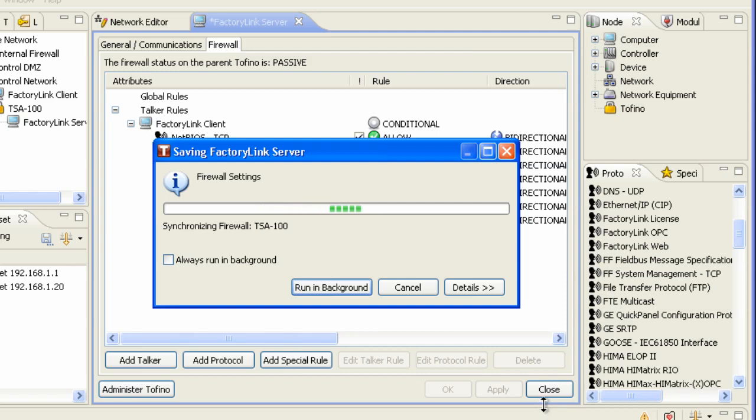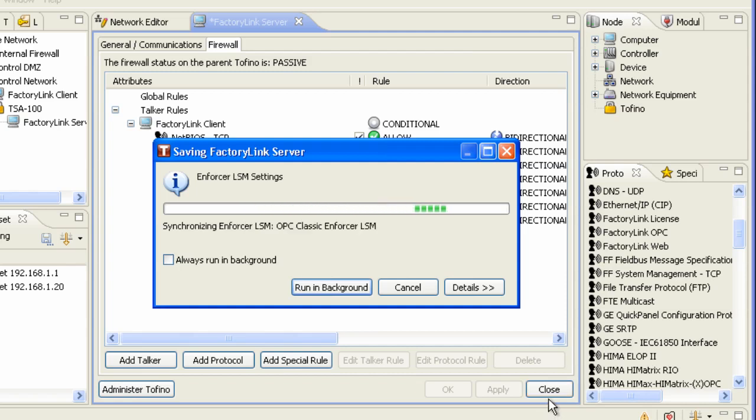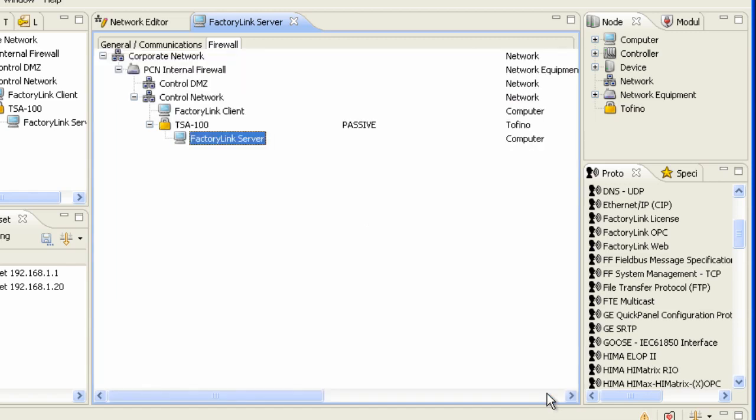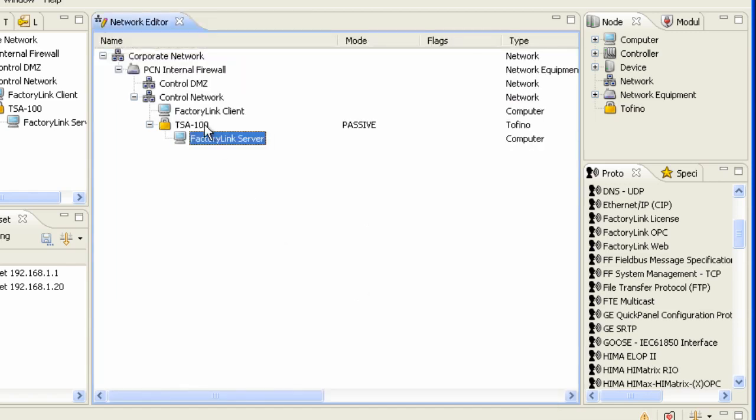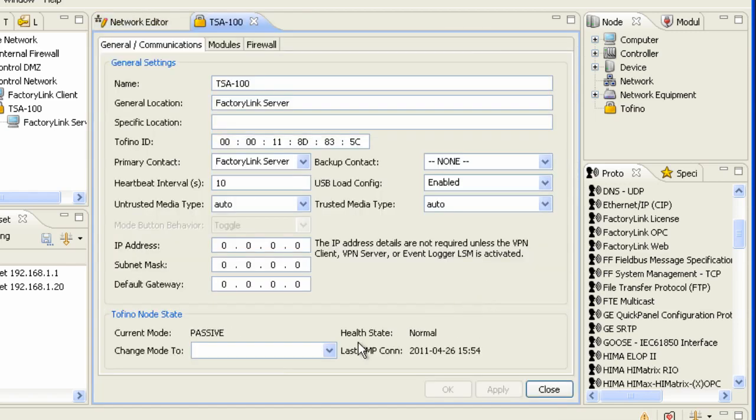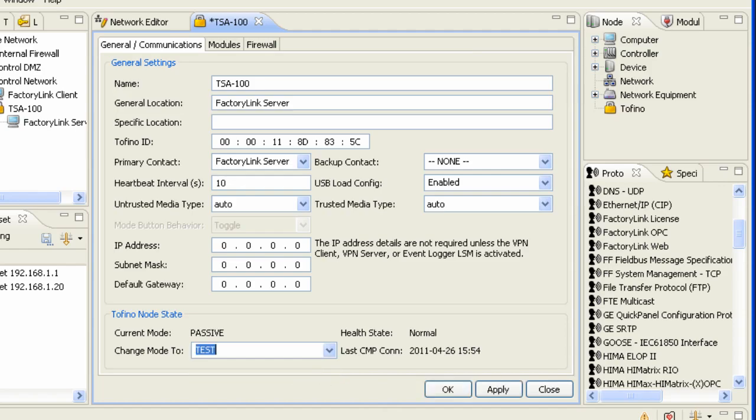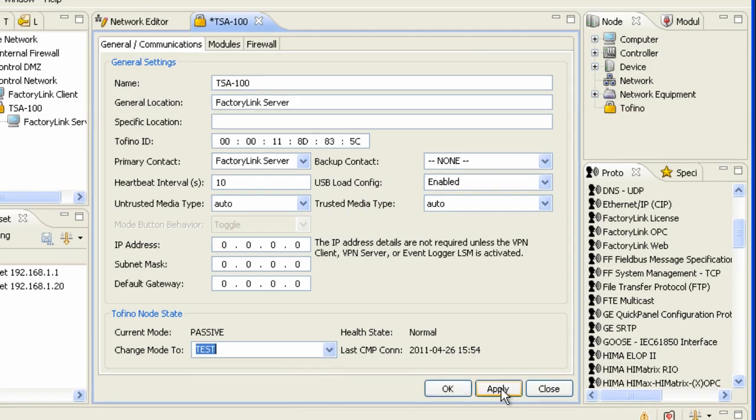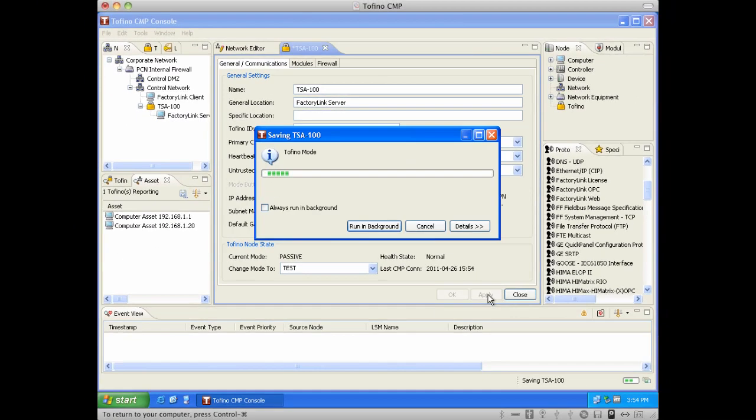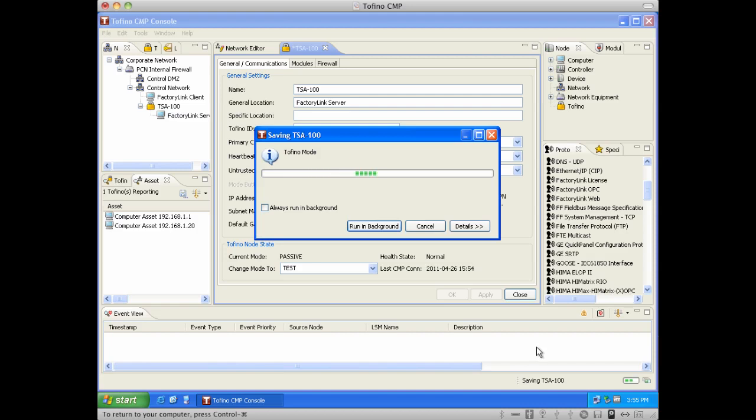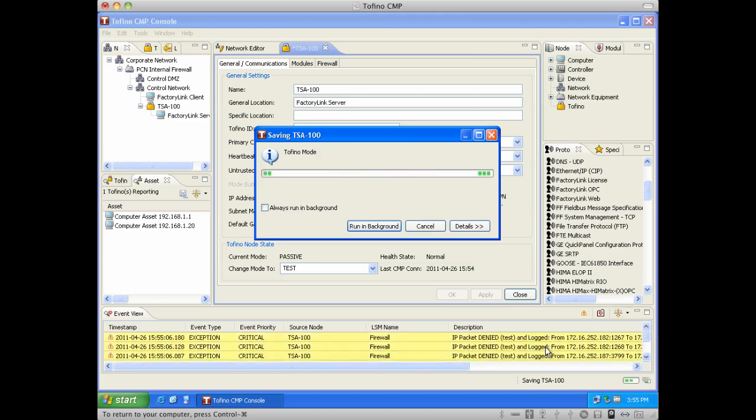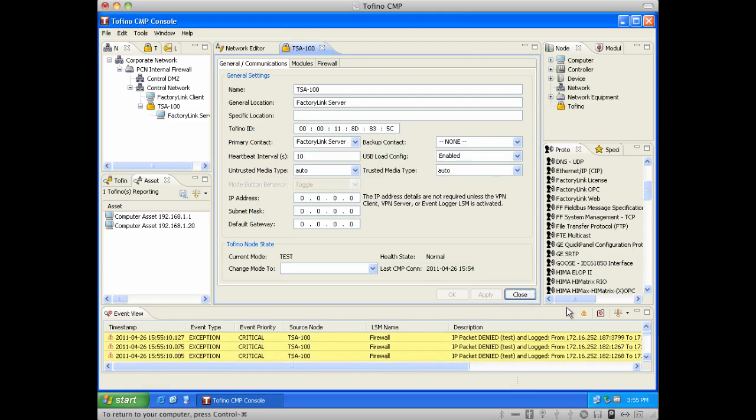And now a very powerful feature of the Tofino security appliance, which makes it perfectly suited for SCADA environments, is the ability to put this in what's called the test mode. And by doing so, it will actually run all of the packets through the rules, yet it will not block or drop any of these packets. And what we're going to see down here on the bottom is we're going to see now the generation of a bunch of alerts, which would signify packets that would not pass any of those pre-configured rules.